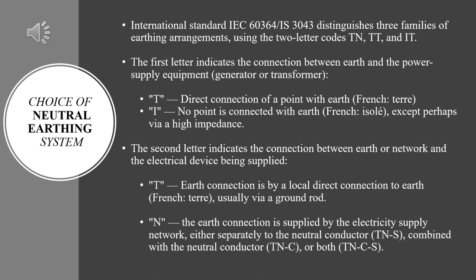The second letter indicates the connection between earth or network and the electrical device being supplied. T means the earth connection is by local direct connection to earth, usually via a ground rod. N denotes the earth connection is supplied by the electricity supply network, either separated from the neutral conductor, that is TNS, combined with the neutral conductor, that is TNC, or both, that is TNCS.